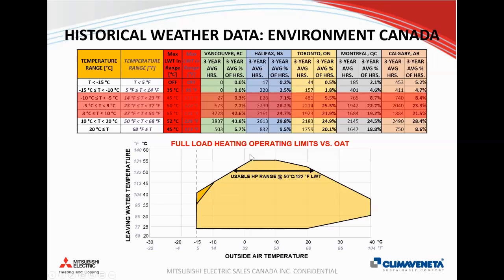And it sounds good, but whenever you look at the operating envelope, you'll see that you can only use a 55 degree supply between +3 and +10 degrees Celsius. As it gets colder than 3 degrees Celsius, the maximum leaving water temperature that you can get from the heat pump will decrease. And so will the capacity and COP, which we'll take a look at on some other slides.